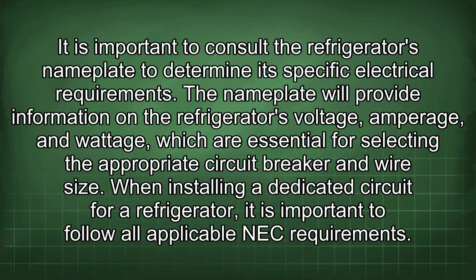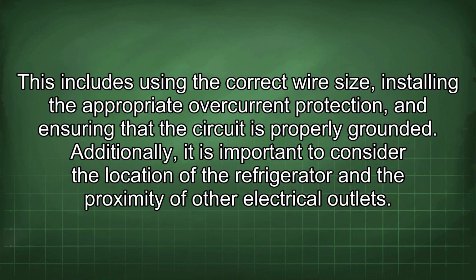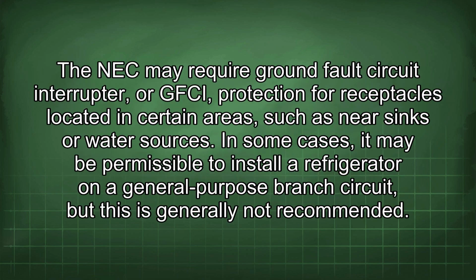The nameplate will provide information on the refrigerator's voltage, amperage, and wattage, which are essential for selecting the appropriate circuit breaker and wire size. When installing a dedicated circuit for a refrigerator, it is important to follow all applicable NEC requirements. This includes using the correct wire size, installing the appropriate overcurrent protection, and ensuring that the circuit is properly grounded. Additionally, it is important to consider the location of the refrigerator and the proximity of other electrical outlets. The NEC may require ground fault circuit interrupter, or GFCI, protection for receptacles located in certain areas, such as near sinks or water sources. In some cases, it may be permissible to install a refrigerator on a general-purpose branch circuit, but this is generally not recommended.